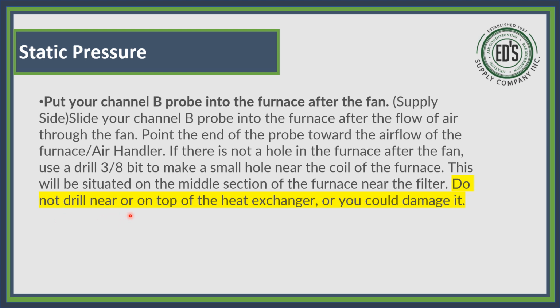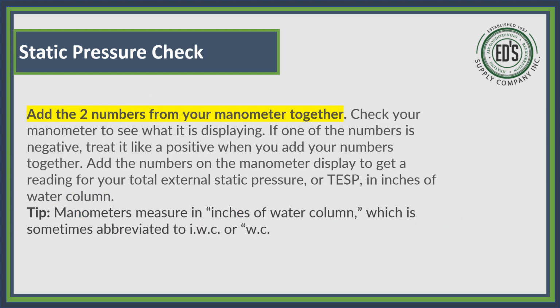Do not drill near or on top of the heat exchanger. You could damage it, so try to go just past that. You add the two numbers together. Do not subtract them. Add them together. Check your manometer to see what the display is. And like I said, keep in mind that 3 is too high on return. You want to see 2 and 1 on return, or 0.